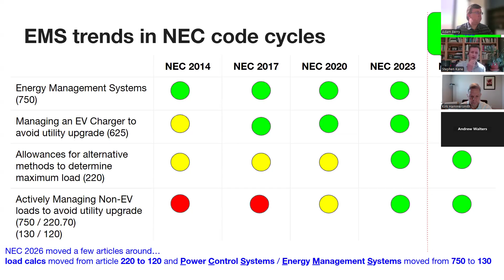Ultimately, Article 220.70 in the load calculation section tells us that as long as we're compliant with Article 750.30 and following the definitions of an EMS, the EMS shall be considered a continuous load for the purposes of load calculations. So it's really just the set point, the maximum ampere set point.